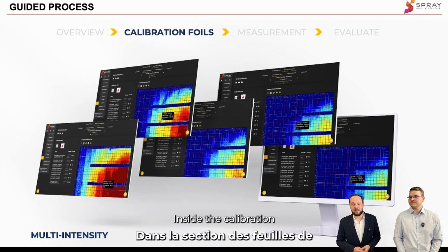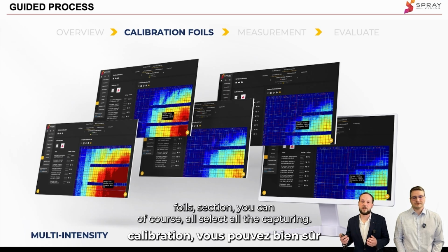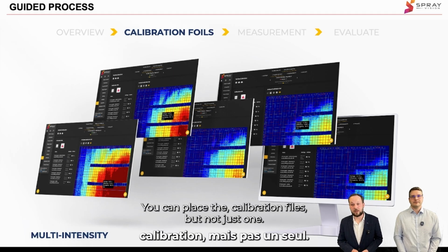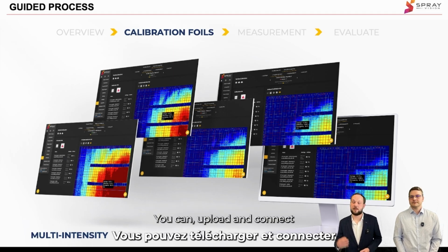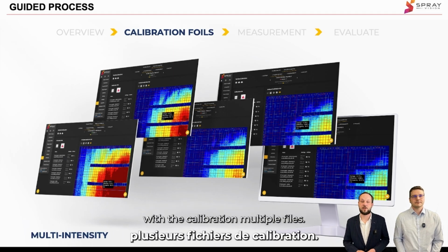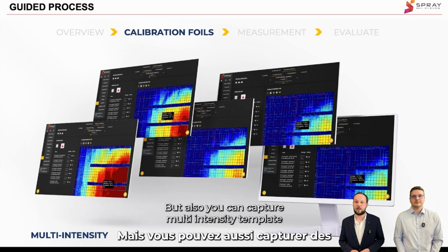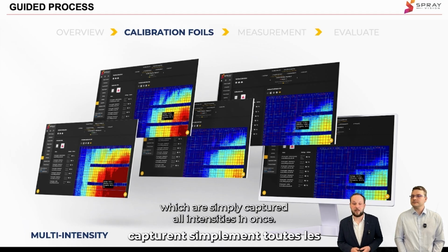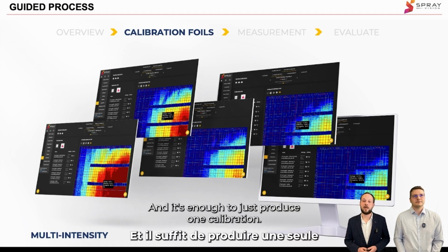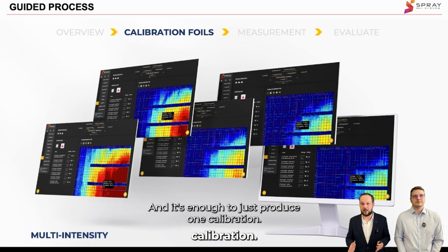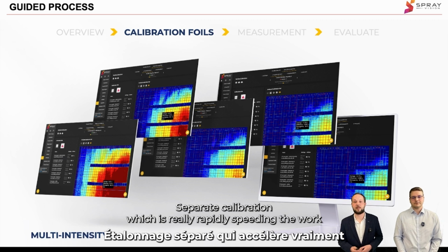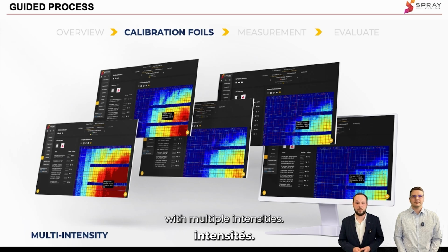Multi-intensity. Inside the calibration foils section, you can of course select the capturing, you can place the calibration foils, but not just one. You can upload and connect multiple calibration foils, but also you can capture a multi-intensity template, which simply captures all intensities at once, and it's enough to produce just one calibration, and the system will generate a separate calibration for each intensity, which really speeds up the work with multiple intensities.